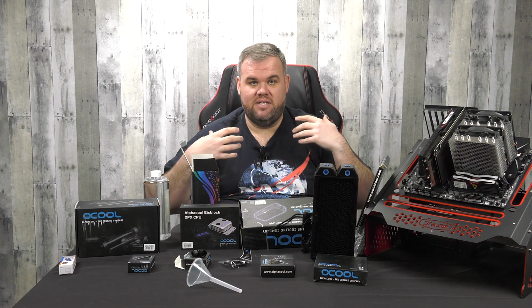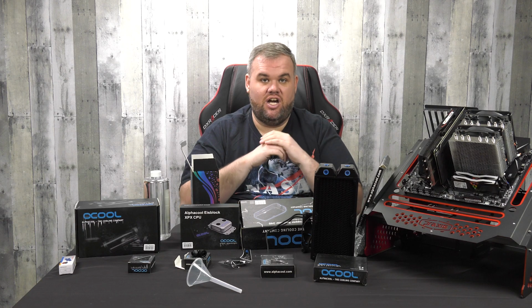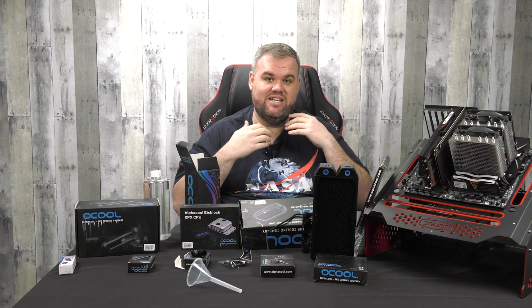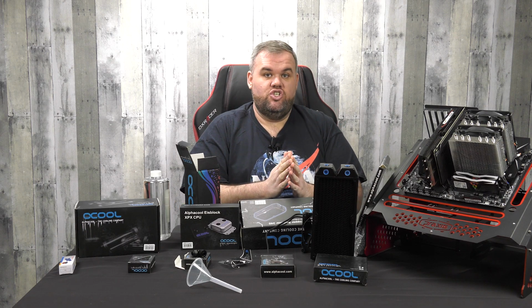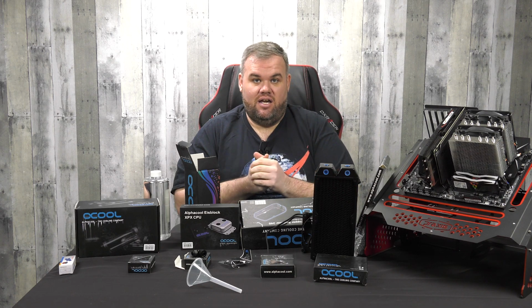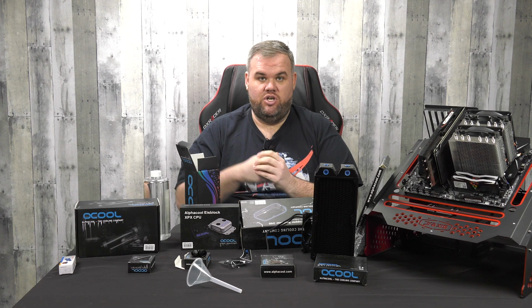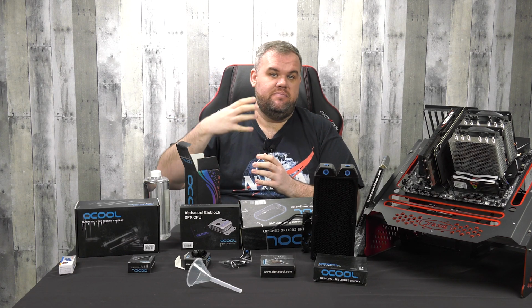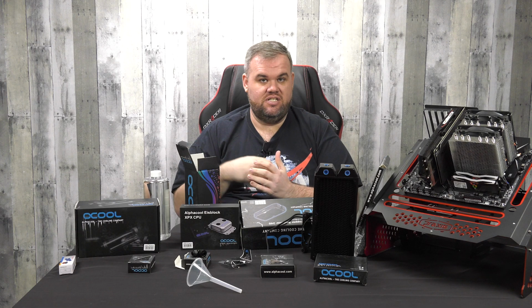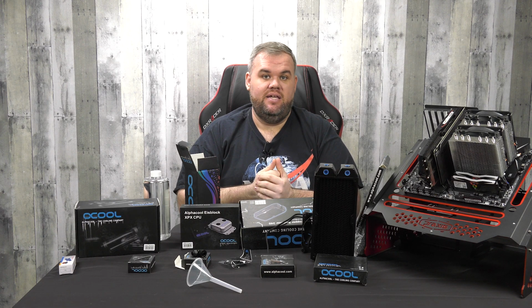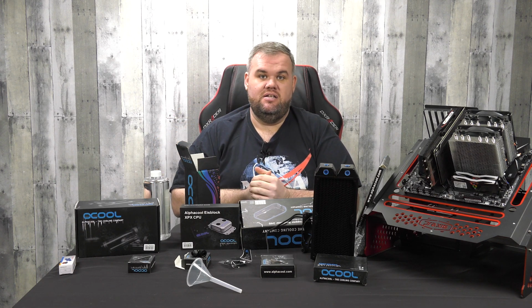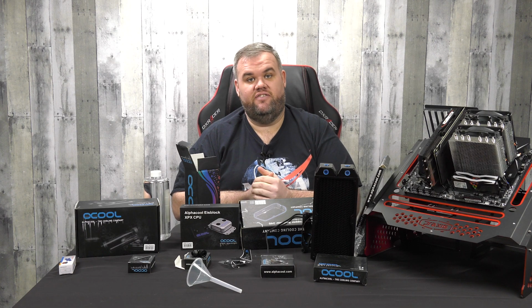Everyone thinks aluminum is toxic to your loop and that's going to cause galvanic corrosion. That's not necessarily the case. When you have galvanic corrosion, that means anything on the anodic index, so any differential in metal on that index, which is specifically speaking to metallurgy, can cause galvanic corrosion.